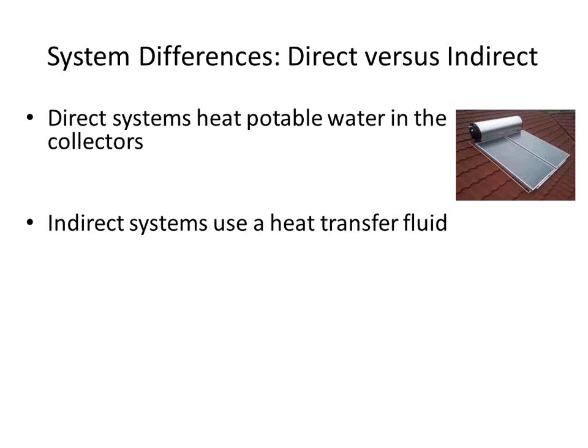The advantage of direct systems is they're very efficient and they're very cost effective. You have fewer components, so they work really well. Water is a better heat transfer mechanism than glycol, so direct systems do work better than indirect systems, all other things being equal. The reason we don't see them used in New England at all is, unfortunately, water freezes below 32 degrees. It gets below 32 degrees often up here. In fact, it was below 32 degrees last night. I was surprised to find. And water expands when it freezes. So anytime you have a direct system on a roof, you either can't use it if it's freezing outside, or you have to have very, very robust ways of making sure that the water gets out of the system before you reach a freezing point, in which case the system's not going to run when the system is at or below freezing.